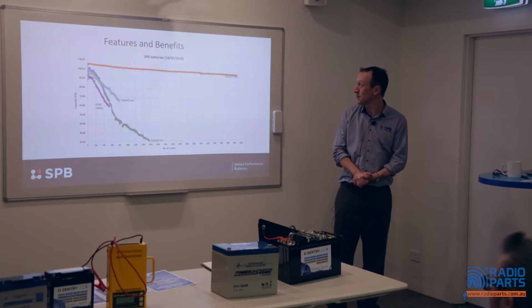The recommended charging range is 20% of the ampere hour capacity. Lead acid, what is it? They say a maximum. With lead acid, you've heard about charge rates, 20% of C. Optimum amount of charge is 10%. They say the maximum amount of charge for a lead acid is about 20% of C. 100 ampere hour battery, 20 amps maximum. Ideally, 10 amps. And the charge is cheaper too, trust me. Optimum is about 10 amps.